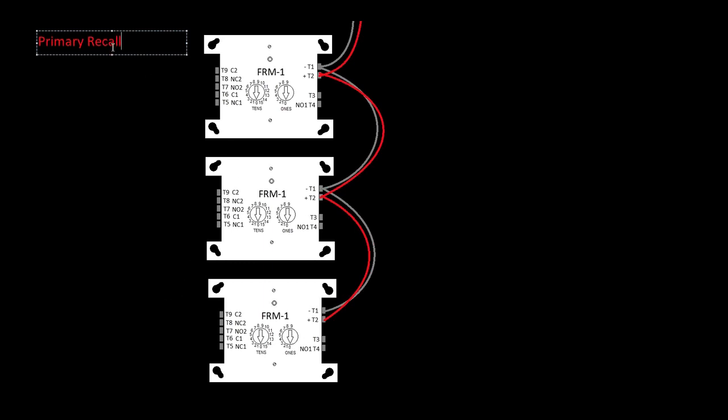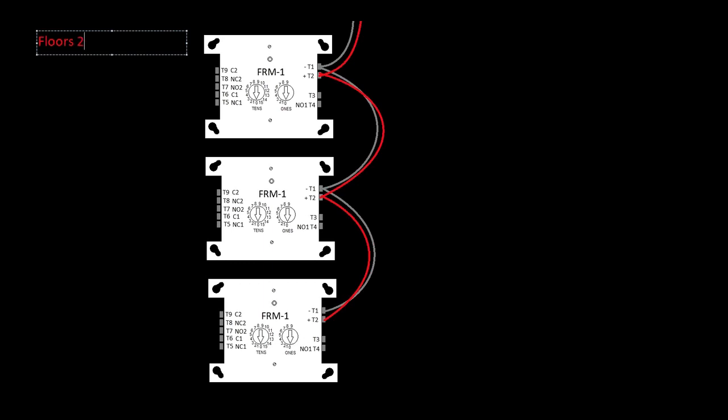We're going to, I would label these relays primary recall, alternate recall, and fire hat flash. But when you're taking your label maker out and you're actually writing on the module or when you're labeling the wires that are going in the controller, this is how I've been labeling these the last few years. I would say something like all floors but one, or, you know, and in some buildings it's easy because you could say something like floors two through ten or two through four, plus basement, something like that to indicate, particularly when you're labeling your wires, so that there's no confusion between you and the elevator guy.